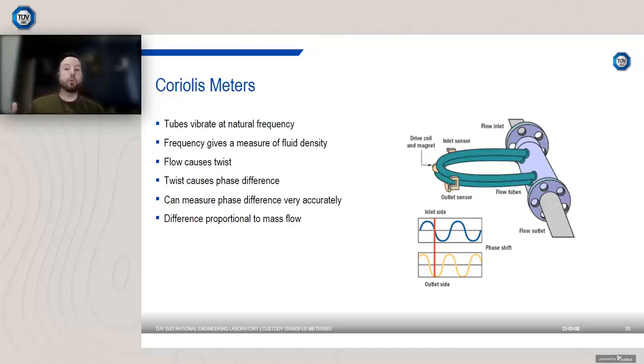When you've got flow going through the Coriolis meter, flow causes the measuring tubes to twist. Now, this twist causes a phase difference between the inlet and the outlet sensor. So if you don't have any flow, you shouldn't have any twist, you shouldn't have any phase difference, so the phase shift should be zero. So when you've got flow, and you measure this phase difference, the difference is proportional to the mass flow of the fluid. Now that's the big advantage of this meter. It will measure mass flow rate, whereas previous technologies typically are volumetric or velocity-based devices. They'll need other measurements like a densitometer in order to give you the mass flow rate of the fluid, whereas Coriolis meters can give you that directly.